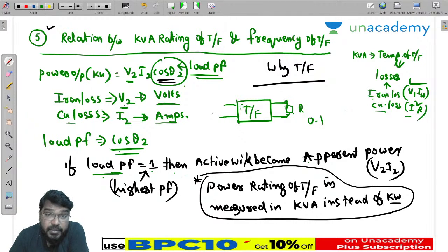Okay, Revati, have we got it now? Why is it a kVA rating? It is measured in the kVA rating. The rating of any electrical machine is designed by the temperature rise. Got my point? So temperature rise means losses.